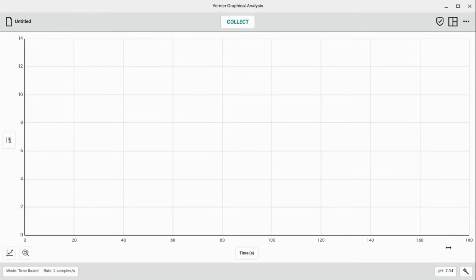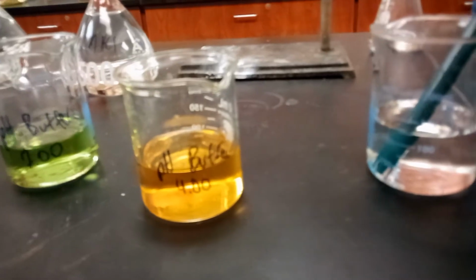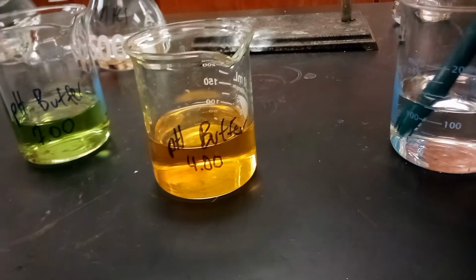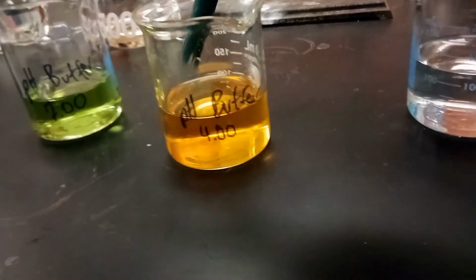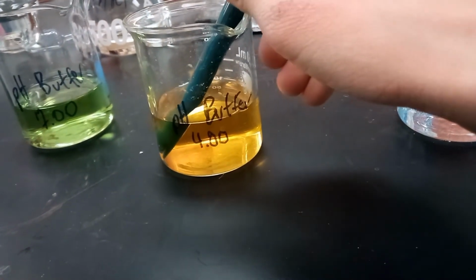So what we're going to do is we're going to go to the bottom here, click the sensor actions button, and press calibrate in order to get our 2-point calibration system working. As you can see, it's asking for the first known value, so we're going to put it into a buffer system whose pH is known. Starting with the pH buffer that reads 4.0 that you can see here, we'll move the pH electrode into this buffer like so.